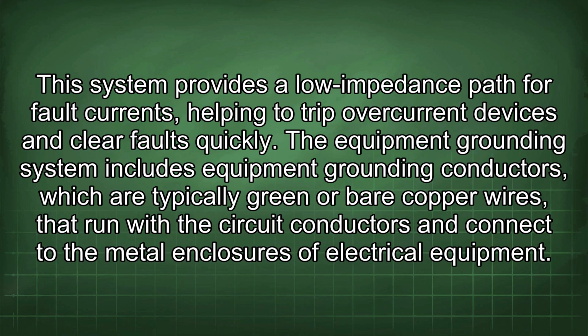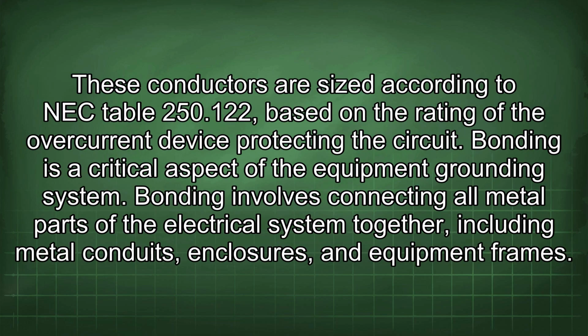In addition to the grounding electrode system, each building must have an equipment grounding system. This system provides a low impedance path for fault currents, helping to trip overcurrent devices and clear faults quickly. The equipment grounding system includes equipment grounding conductors, which are typically green or bare copper wires that run with the circuit conductors and connect to the metal enclosures of electrical equipment. These conductors are sized according to NEC Table 250.122, based on the rating of the overcurrent device protecting the circuit.